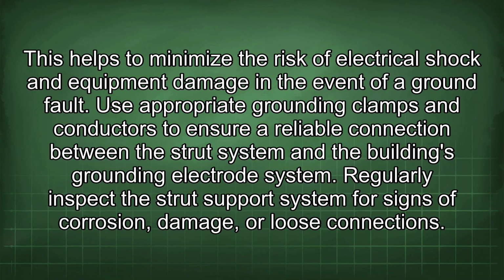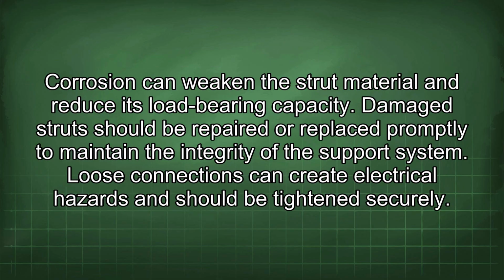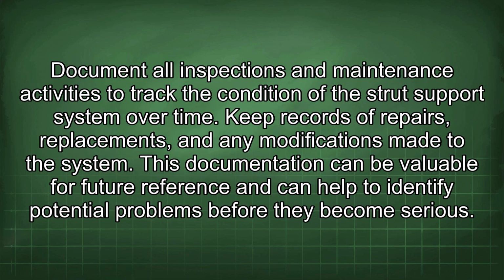Regularly inspect the strut support system for signs of corrosion, damage, or loose connections. Corrosion can weaken the strut material and reduce its load-bearing capacity. Damaged struts should be repaired or replaced promptly to maintain the integrity of the support system. Loose connections can create electrical hazards and should be tightened securely. Document all inspections and maintenance activities to track the condition of the strut support system over time.